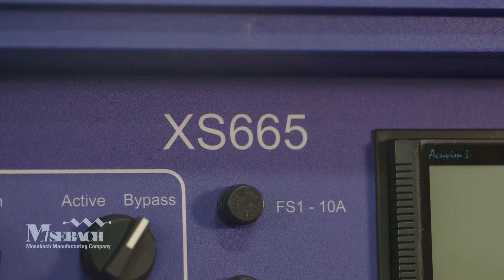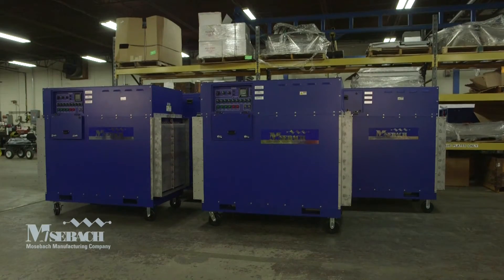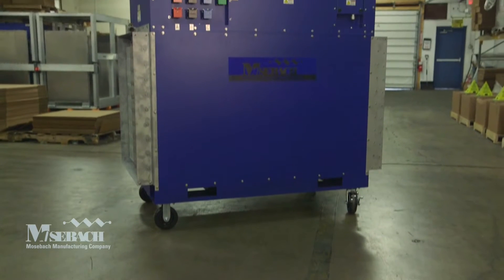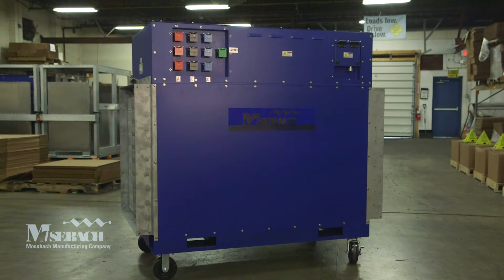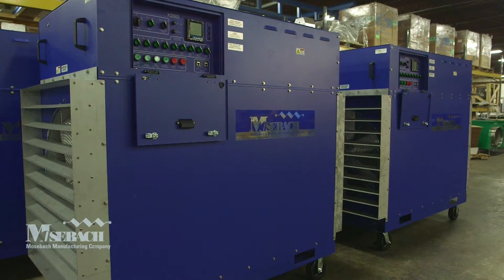Mosebach's XS665 offers a 665 kilowatt load at 480 volts or a 500 kilowatt load at 416 volts. It has 5 and 3.75 kilowatt step resolution respectively.